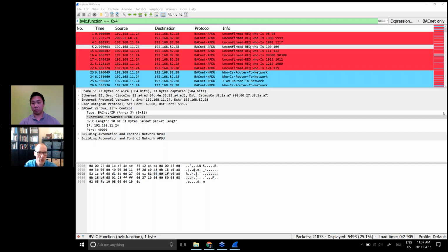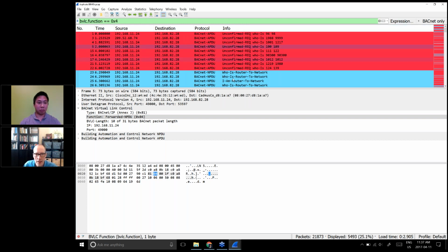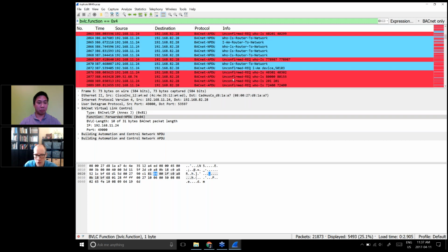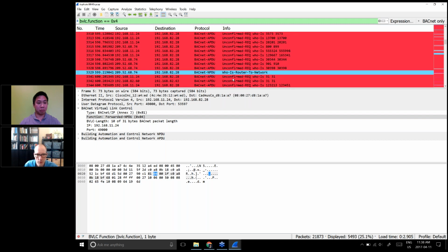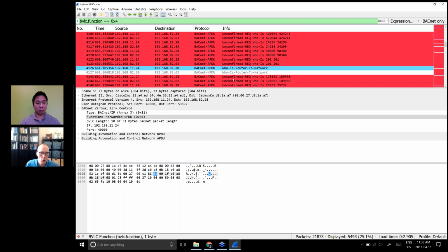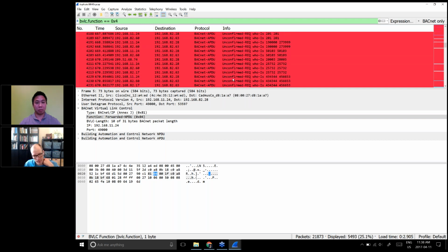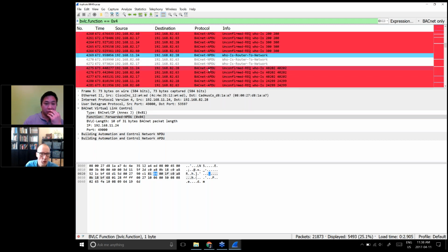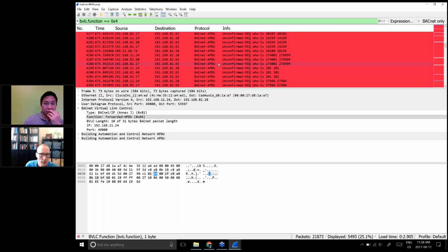Now scroll down to, I think it was 673, something like that from memory. Again, the problem doesn't exist at this point. There are no duplicate BBMDs at the beginning of the capture, so there's nothing defined at this point. So if you start going down, that's when things are going to go a little bonkers again. Again, the IO graph would be helpful because we would see the traffic spike up. Keep going down a bit further, because I know it was right in here when I enabled the whole thing. Yeah, that's good there. You just went past it. Go back up a bit. Actually, anywhere in there is fine.